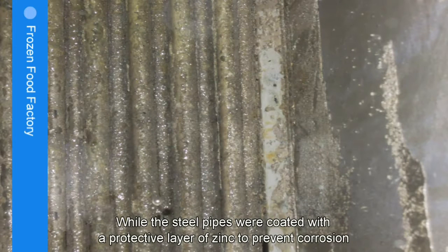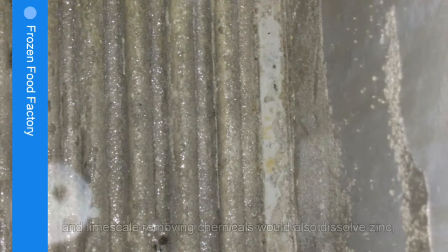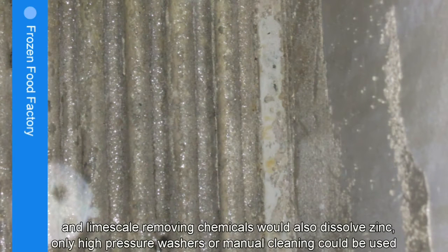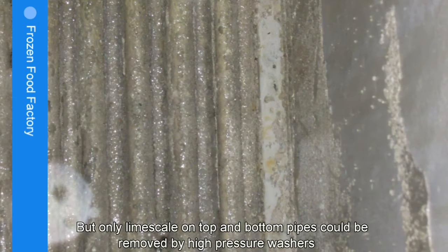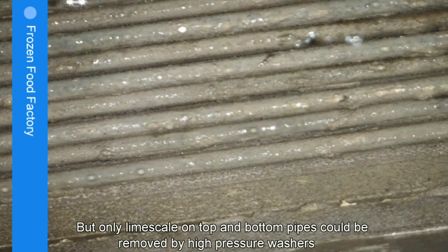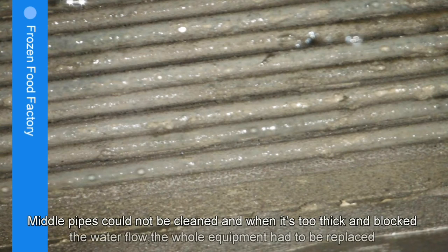While the steel pipes were coated with a protective layer of zinc to prevent corrosion, limescale removing chemicals would also dissolve zinc. Only high-pressure washers or manual cleaning could be used. But only limescale on top and bottom pipes could be removed by high-pressure washers. Middle pipes could not be cleaned, and when it's too thick and block the water flow, the whole equipment had to be replaced.